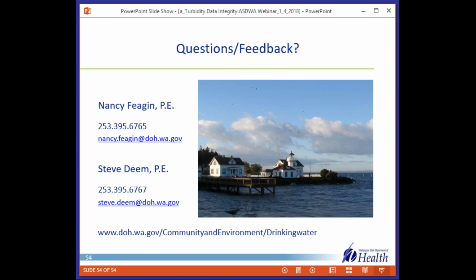Would you change any of your recommendations for raw surface water tap locations associated with LT2, crypto, or E. coli monitoring or similar risk analysis? So if you're referring to signal span, you want to set the raw water turbidimeter to cover the entire range of what you expect to see. So if you expect to see 1,000 turbidity units, you better get a turbidimeter that can handle that, and you probably don't want to cap the data. Right. Absolutely. And generally, you want raw water before sedimentation or anything else. So that could be something at play. You might also have a turbidimeter between sedimentation and your filters, and that might then be expecting to see way less turbidity.